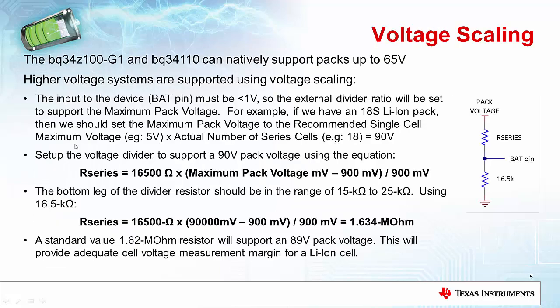So we can also implement voltage scaling for systems where customers need to support much higher level voltages than the gauges can natively support. For example, our BQ34Z100G1 and BQ34110 can natively support pack voltage up to 65 volts. But for higher voltages than that, we can also modify the voltage divider that is used in the system, and then together with some modifications to the flash values, we can actually support these higher level voltages.